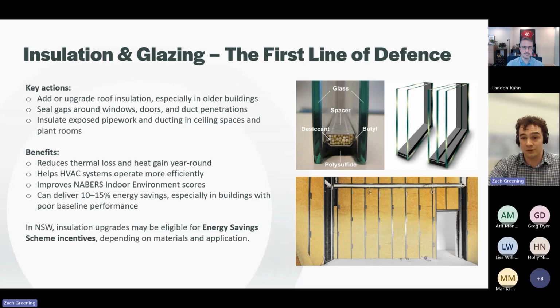Some key actions to consider are upgrading or adding roof insulation, especially in older buildings that may have degraded or minimal coverage; sealing gaps around windows, doors, and duct penetrations, which are often culprits behind hot or cold spots; and insulating exposed pipework and ducting in ceiling spaces and plant rooms. These forgotten areas aren't very glamorous, but they contribute significantly to system inefficiencies, especially in larger commercial facilities.